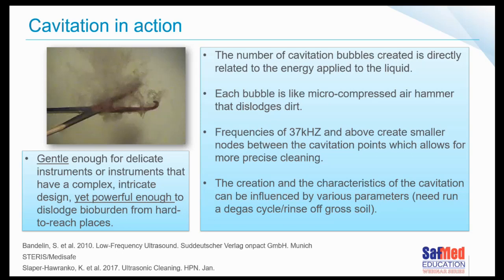Important. Now, this is what we want in healthcare: very precise cleaning. The creation and the characteristics of that cavitation can be influenced by all sorts of things. And that's why we tend to need to do things like run a degas cycle at the beginning of the day or at the beginning of the cycle, depending on whether it's automated or not, and rinse off gross soil. Because if we don't do that, it's going to affect the cavitation process, which then means it affects the cleaning efficacy. So therefore, we are looking for a device that's gentle enough for the delicate instruments, all those instruments that are complex and intricate, but powerful enough to dislodge the bioburden from hard-to-reach places.